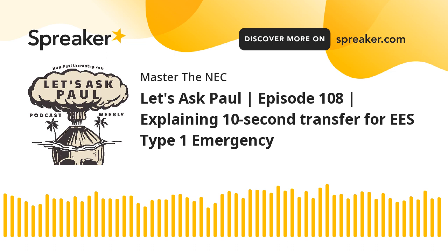So, okay. So this one says, "Hello, Paul. I've been listening to your podcast for the last 2 years and greatly appreciate the content you provide. I had a conversation with a journeyman about 250.64(E)(1), and he informed me that the aluminum conduit needs to be electrically continuous by bonding each end. I had a rebuttal that aluminum is non-ferrous and does not require a supply-side bonding jumper. Non-ferrous metal raceways, and this is a quote, by the way, 'non-ferrous metal raceways, enclosures, and cable armor shall not be required to be electrically continuous,' end of quote, in 250.64(E)(1).